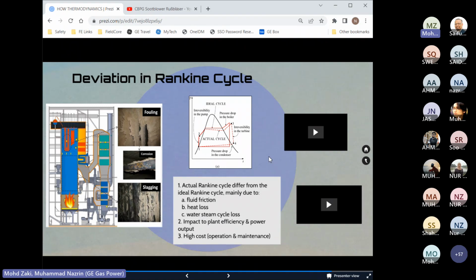So let's say in the paper we say 580 degrees C, maybe actually we cannot achieve 580 degrees C, maybe we only can achieve 560 degrees C. This is due to several conditions, several factors. One of it is fluid friction, heat losses, and also water steam cycle loss. This will impact the plant efficiency and power output, and also contribute to higher operation and maintenance cost.